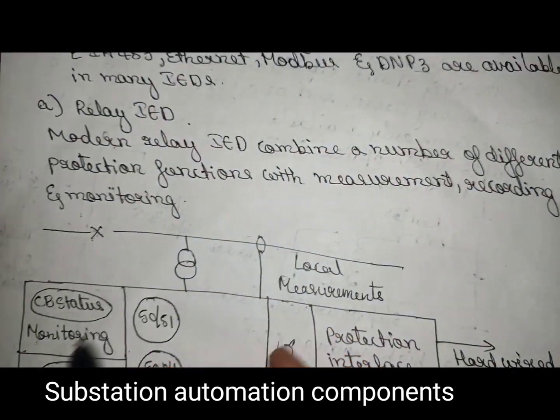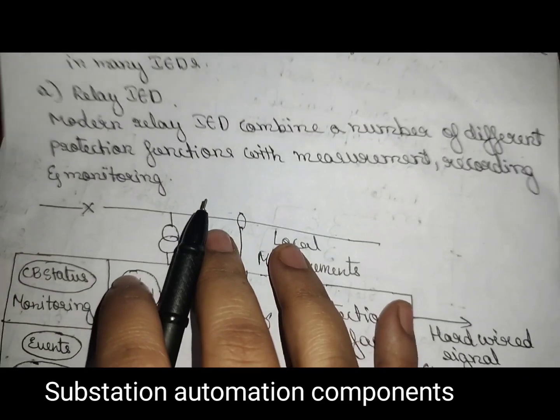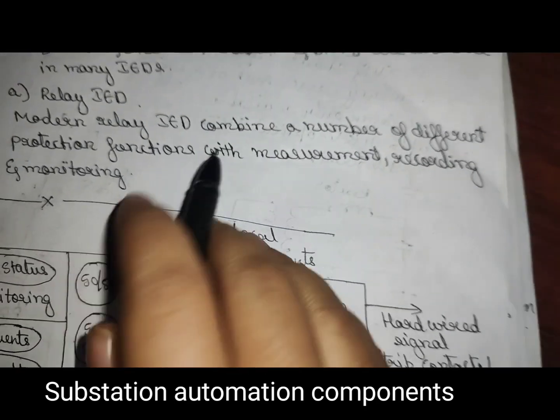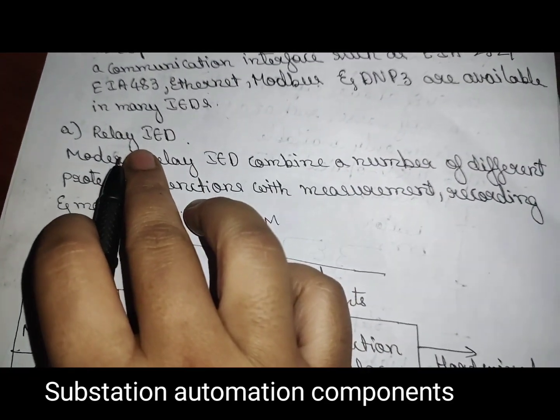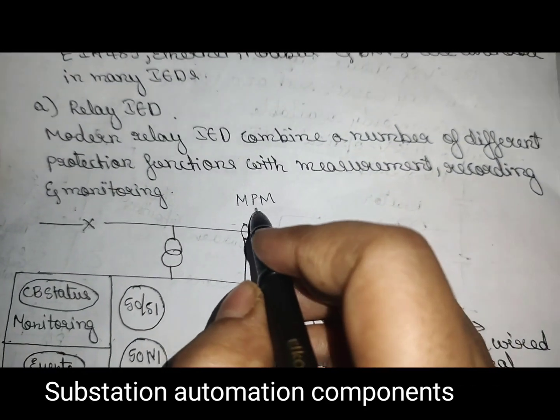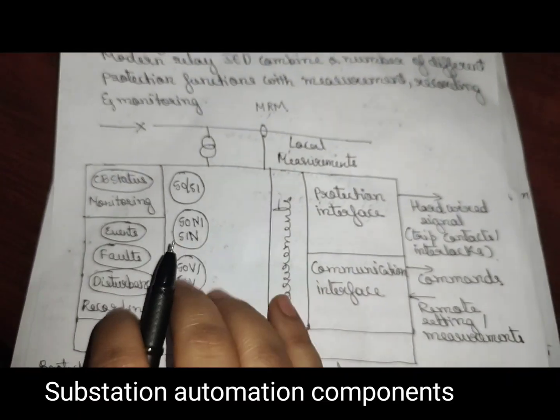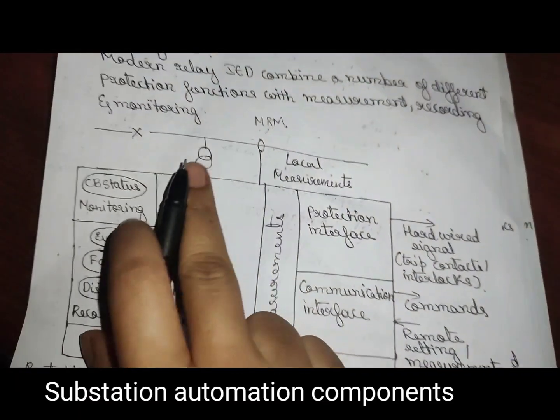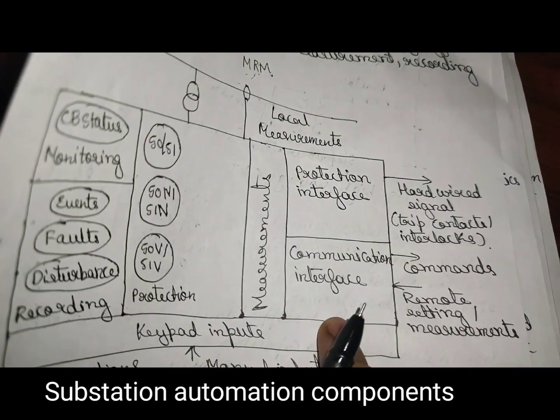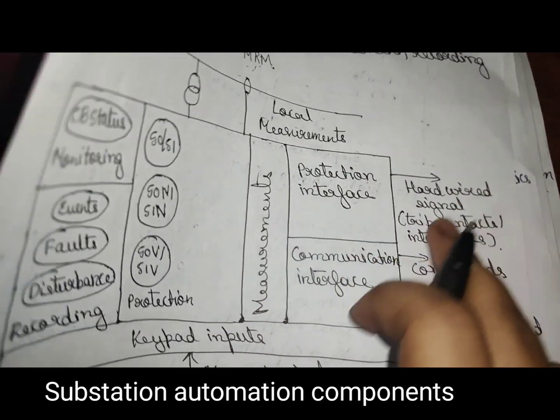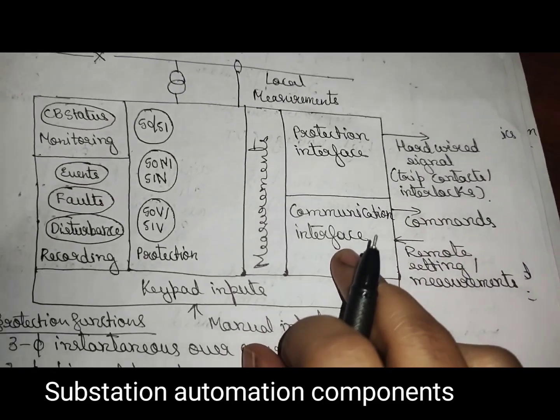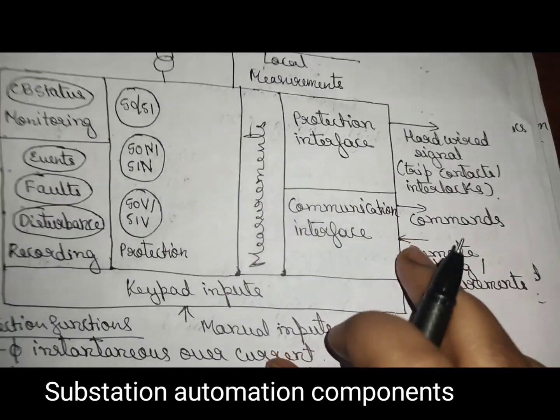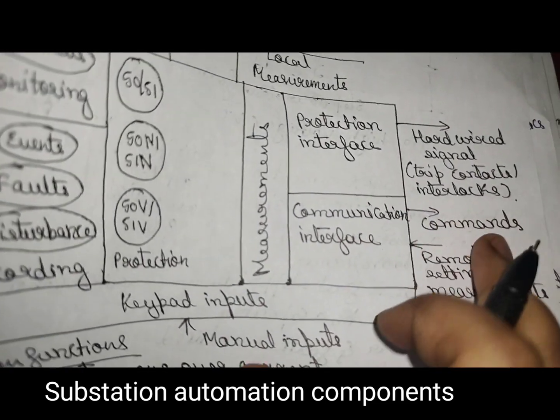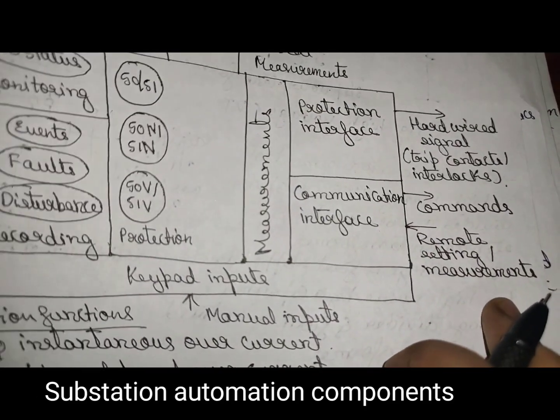So first, relay IED. Modern relay IEDs combine a number of different protection functions with measurement, recording and monitoring. So MRM. So you can observe here the local measurements, protection interface and communication interface. The protection interface will go to the hardwired signal, trip contacts or interlocks. The communication interface carries commands, outputs and inputs also. Outgoing commands are outgoing, and entering remote settings or measurements are entering.